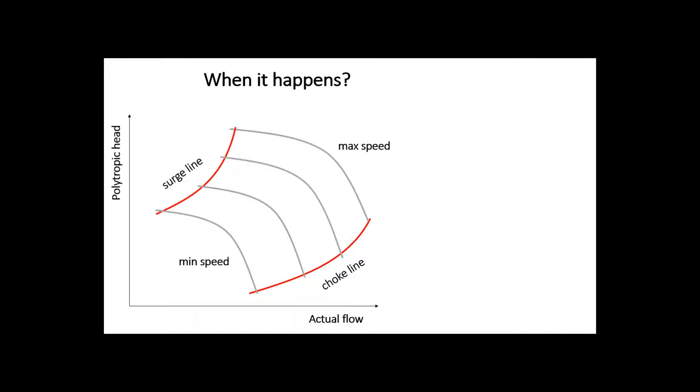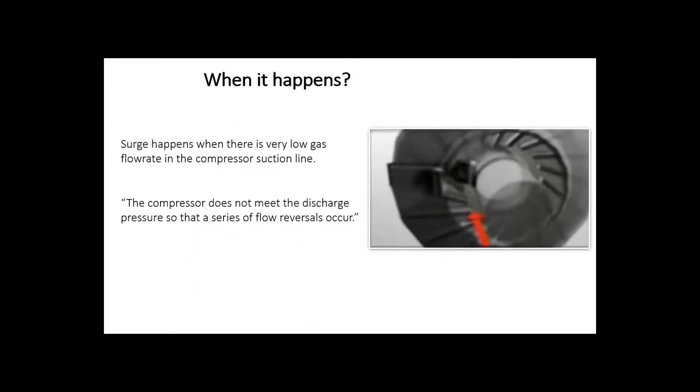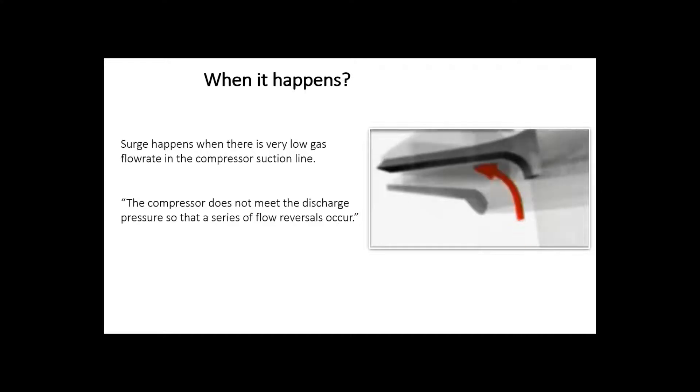The surge point indicates the minimum capacity that the compressor is able to deliver stable operation. This is actually the minimum theoretically operable point of the flow rate, but we always take some margin. The unstable operation, the surge cycle, starts when we fall behind this surge line.